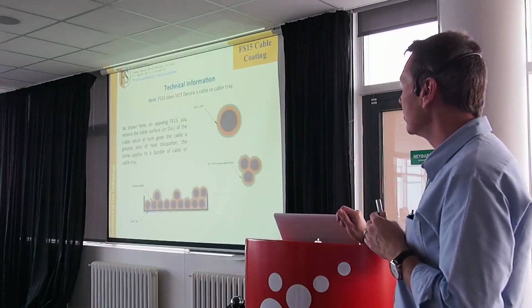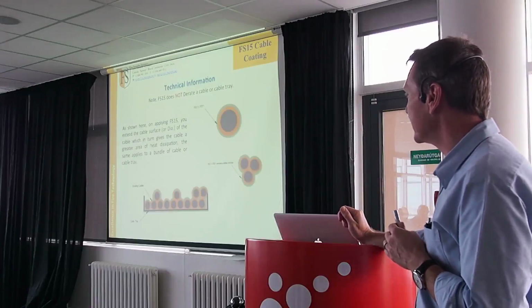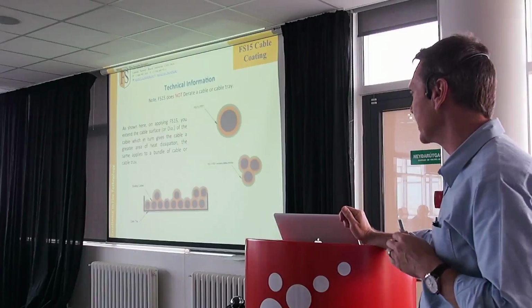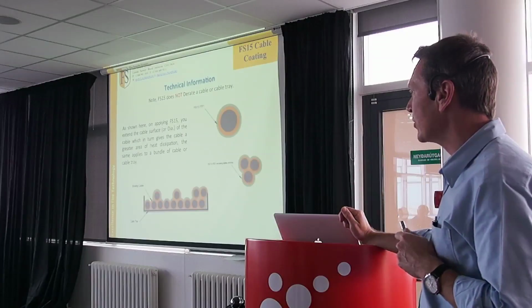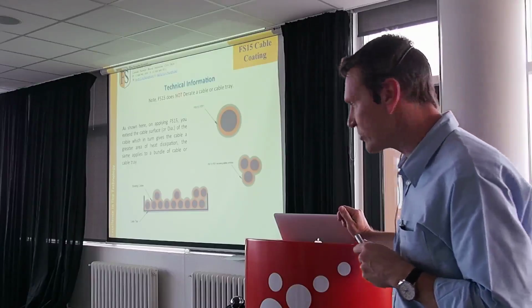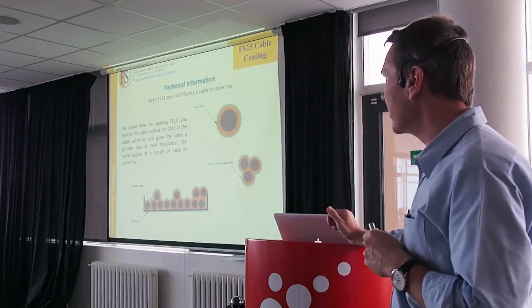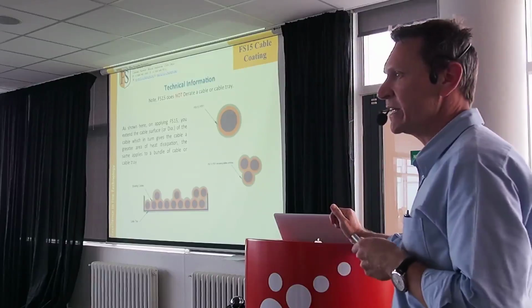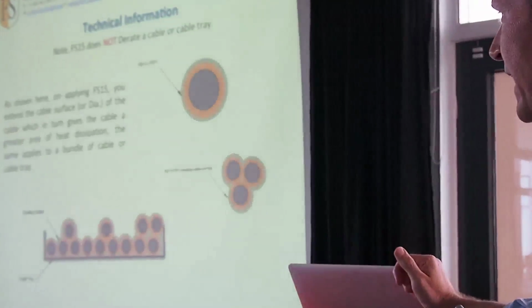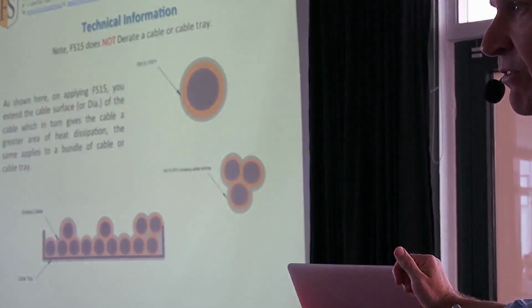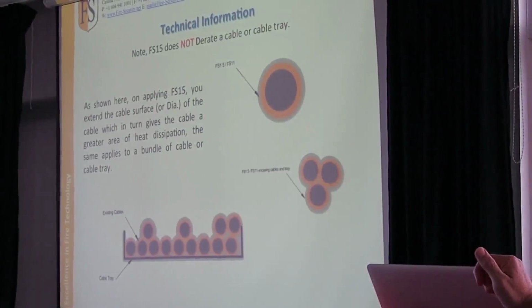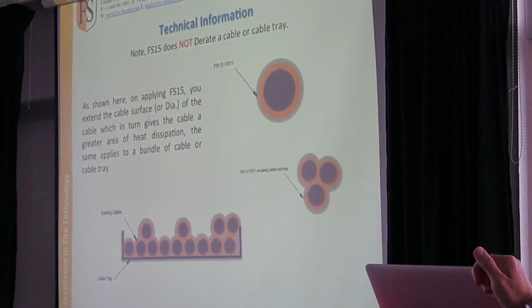So we do not derate a cable or a cable tray. So derating a cable will run at a certain temperature, and when you cover that cable, you'll actually create heat because that temperature can't get out of the cable and it can't run and function properly. So what that facility or what the asset owner will do is turn down the function of that cable. And if that cable's not functioning at maximum capacity, it's not doing its job.